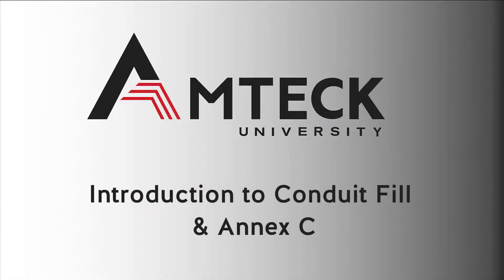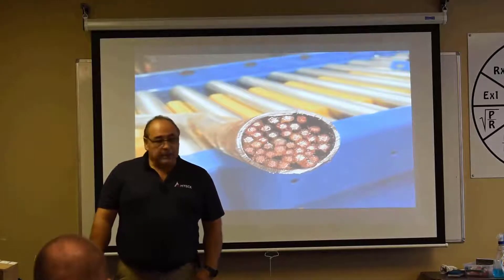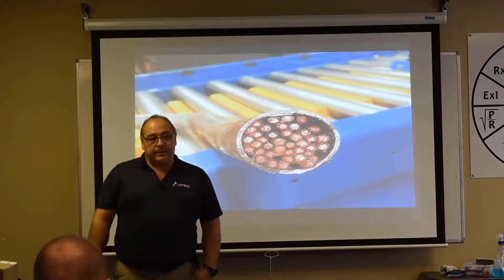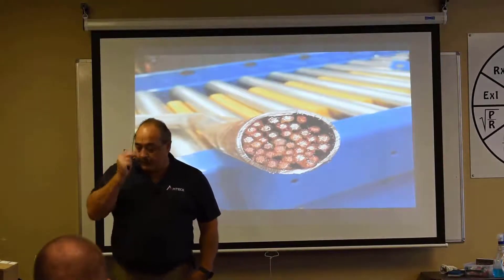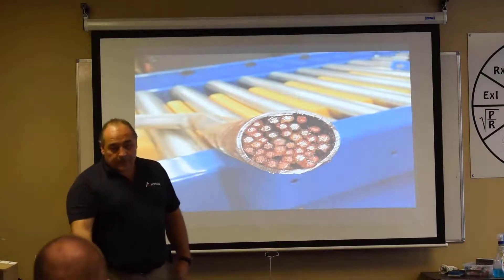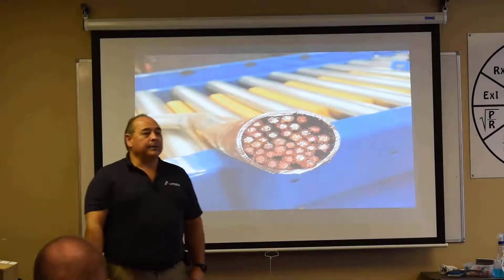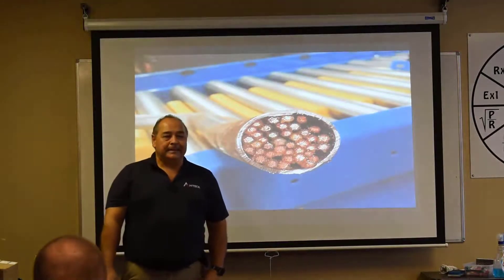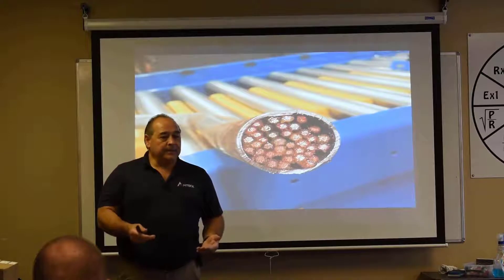We're going to talk about conduit fill. When we talk about conduit fill, I want everybody to understand we're not talking about the ampacity of a conductor. We talked about the ampacity of a conductor a little while ago, where if you get more than three current-carrying conductors in a conduit, you've got to start reducing the ampacity.